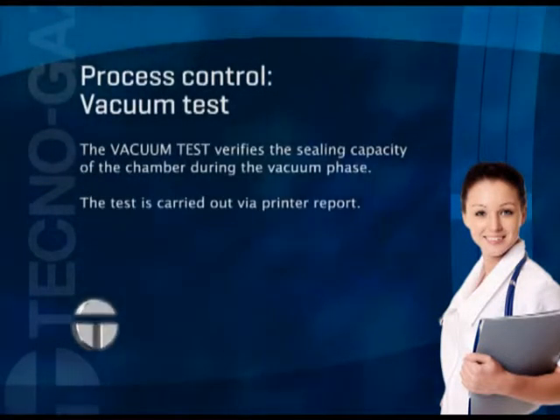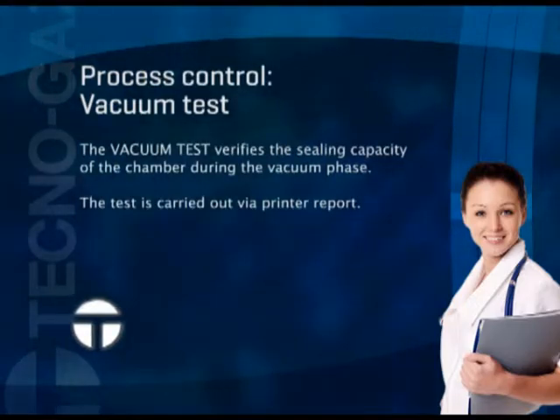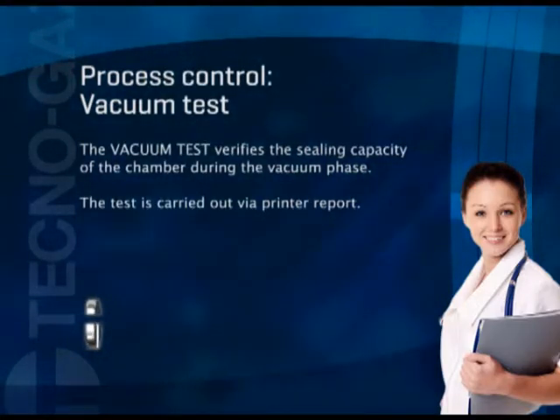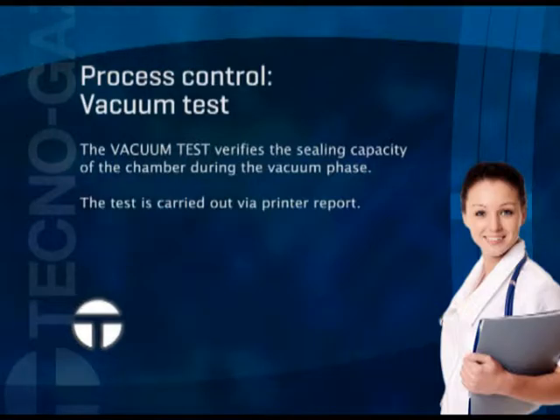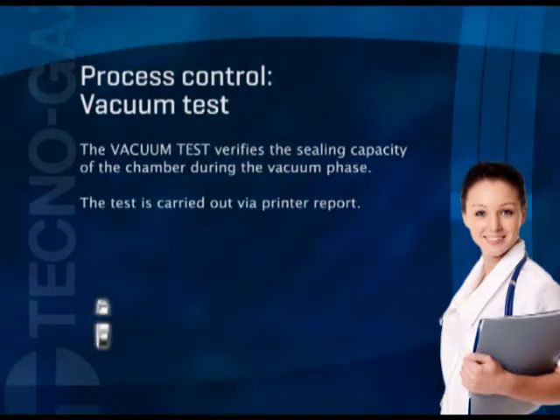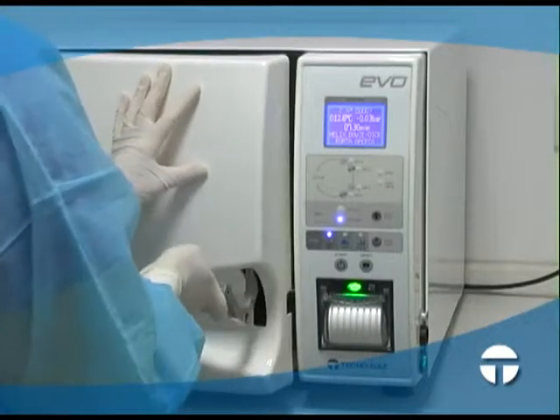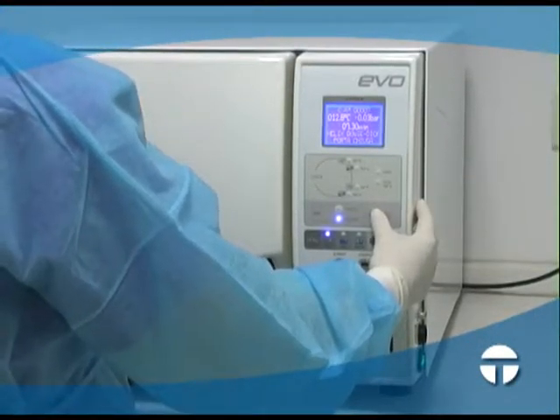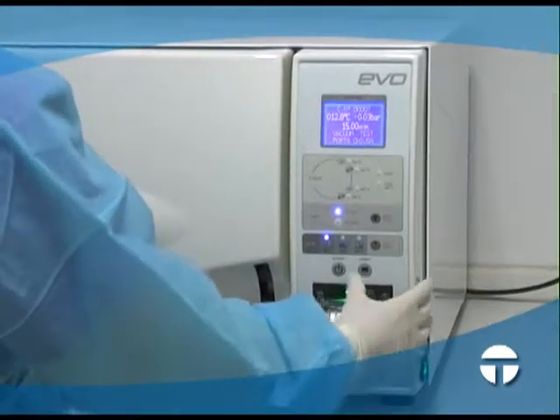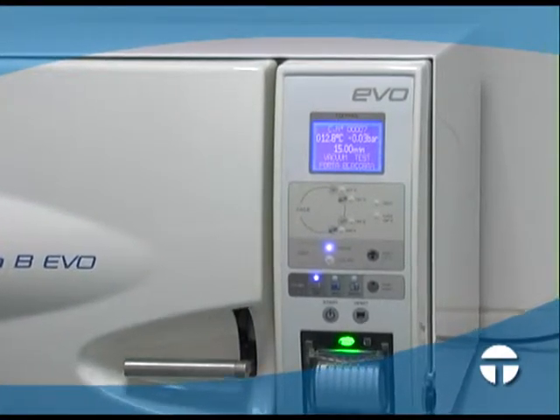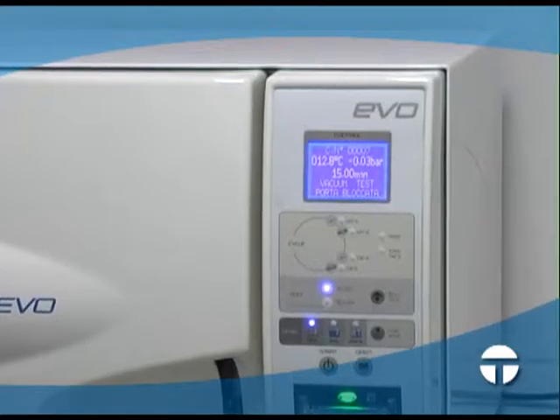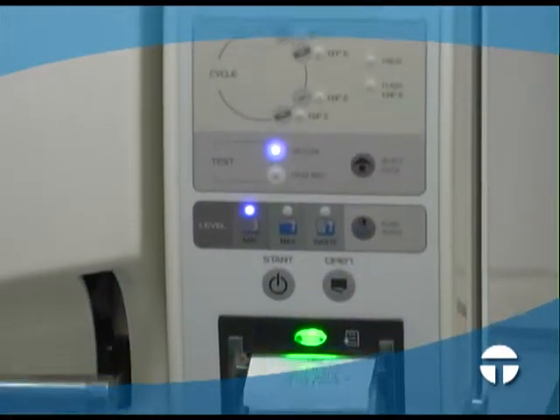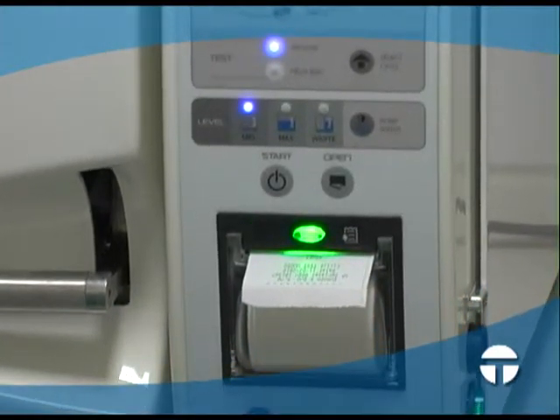Vacuum Test. The vacuum test verifies the sealing capacity of the chamber during the vacuum phase. The test is carried out via printer report. Do not place any type of load in the autoclave. Close the door. Select the vacuum test cycle and start. At the end of the cycle, check the result by examining the printout issued by the printer connected to the autoclave.